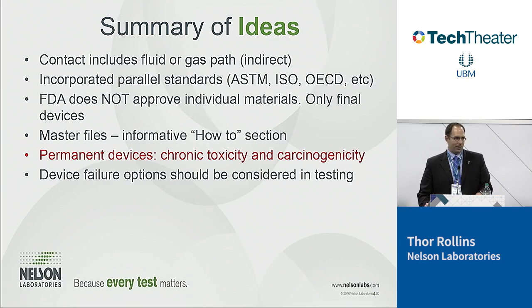So, permanent contacting devices should only be extracted at 50 degrees Celsius, okay? So when we do biocompatibility, we take a device and we extract it in fluid. We put it into some kind of liquid to get the chemicals that come off. We have different temperatures we can do that at.